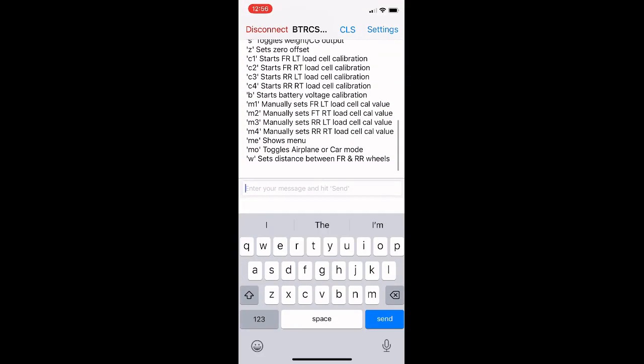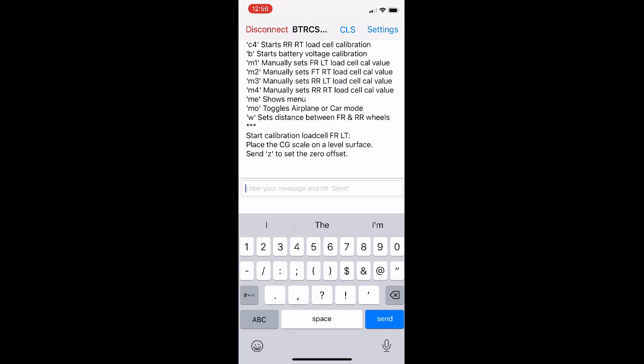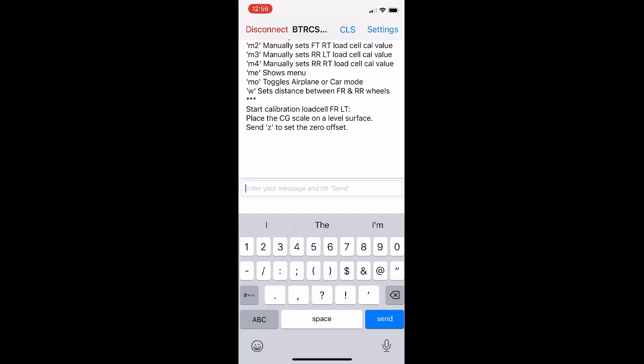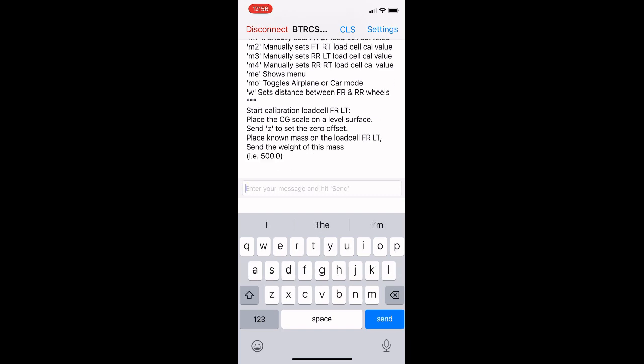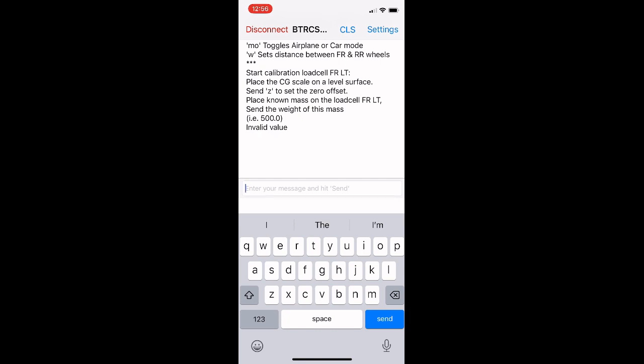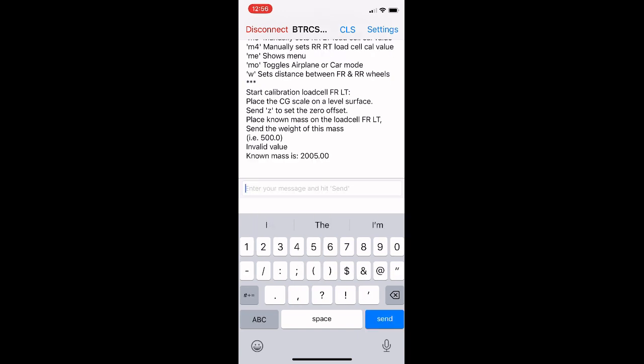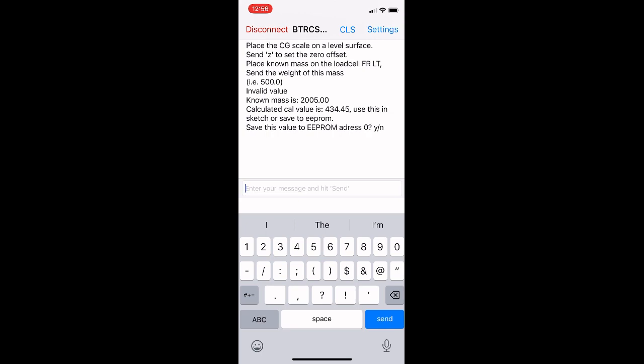So here we have the menu. We type C1 in, and that calibrates the first load cell. It asks you to zero the load cell, so type Z. Then it asks you to put on the known weight, whatever your known weight is. Mine happens to be 2005. Type that in, hit enter, and then it asks you, do you want to save to EEPROM? You can say yes or no.